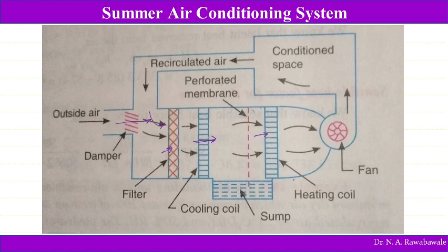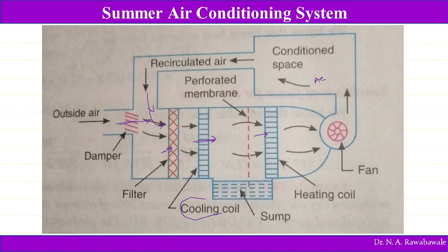The water particles present in the air get condensed and are removed by the perforated membrane, and the air is dehumidified. Then the dehumidified air enters the heating coil to increase its temperature to the required comfort level, because the temperature after the cooling coil is very low — below dew point temperature. The heating coil improves the dry bulb temperature to the required comfort temperature, and then the fan blows this air into the AC space. The water collected from dehumidification drains into the sump.